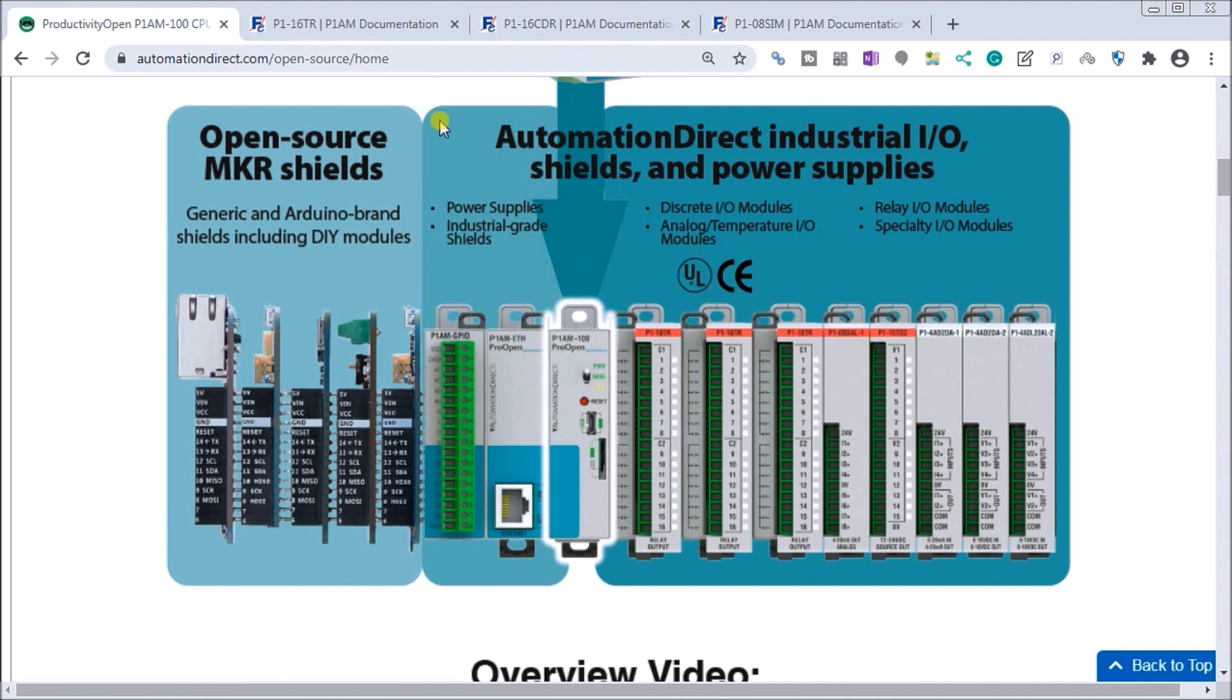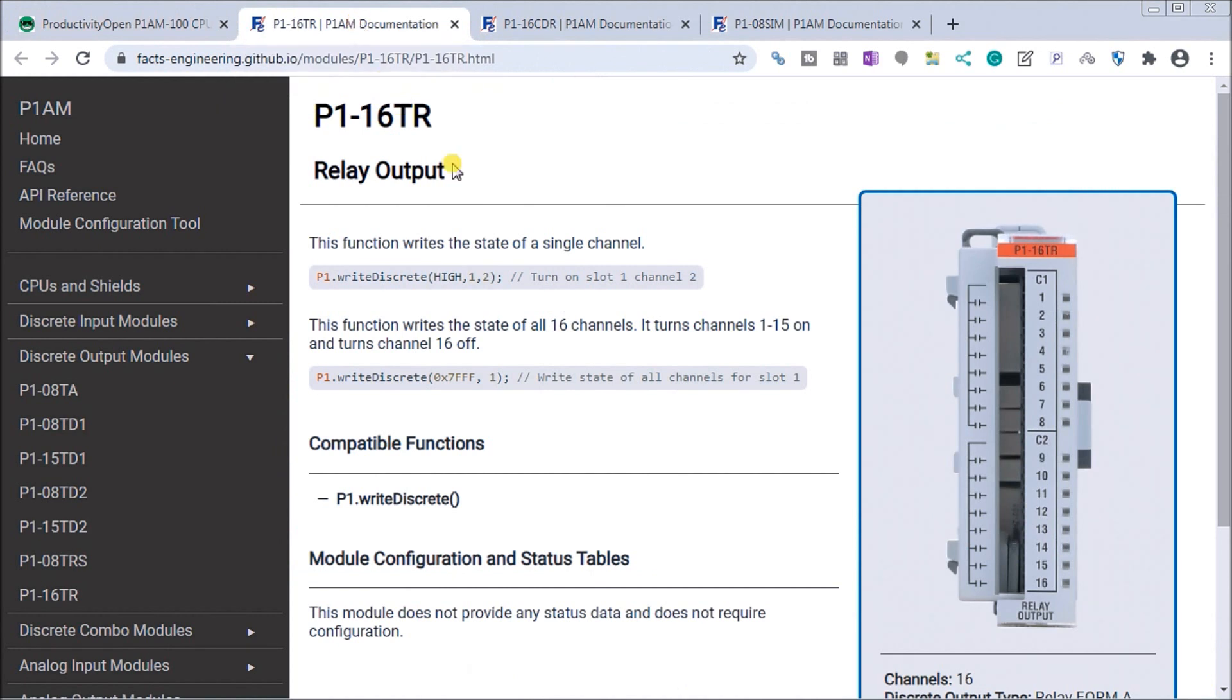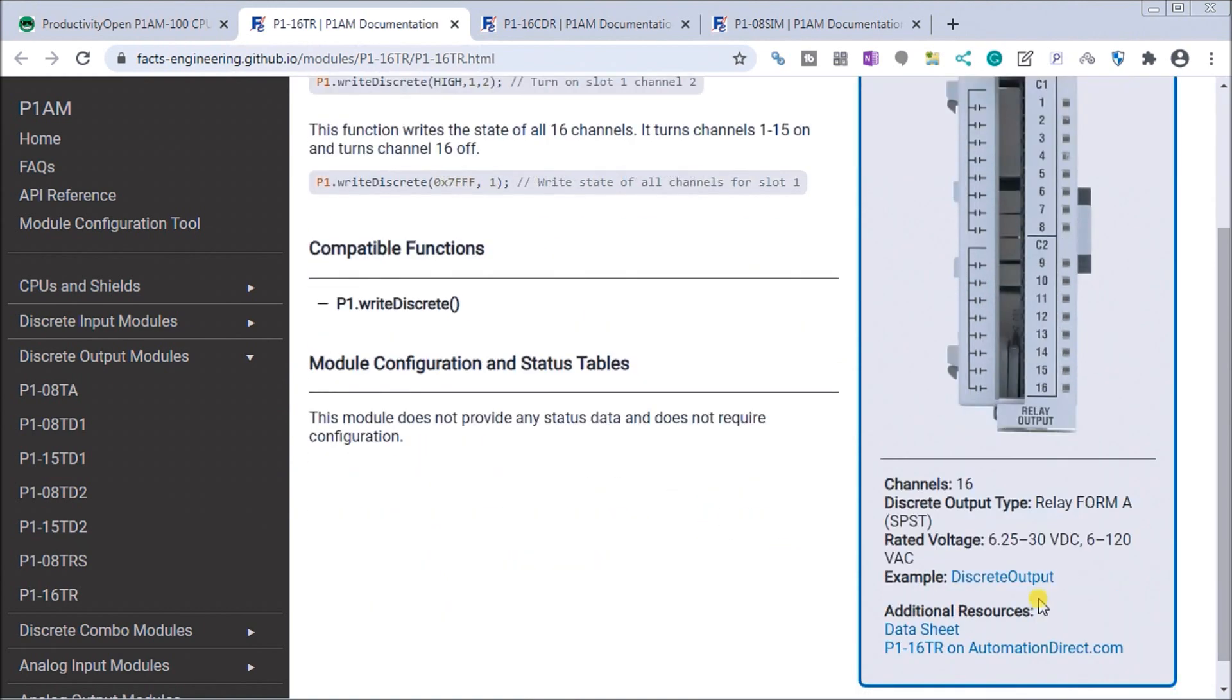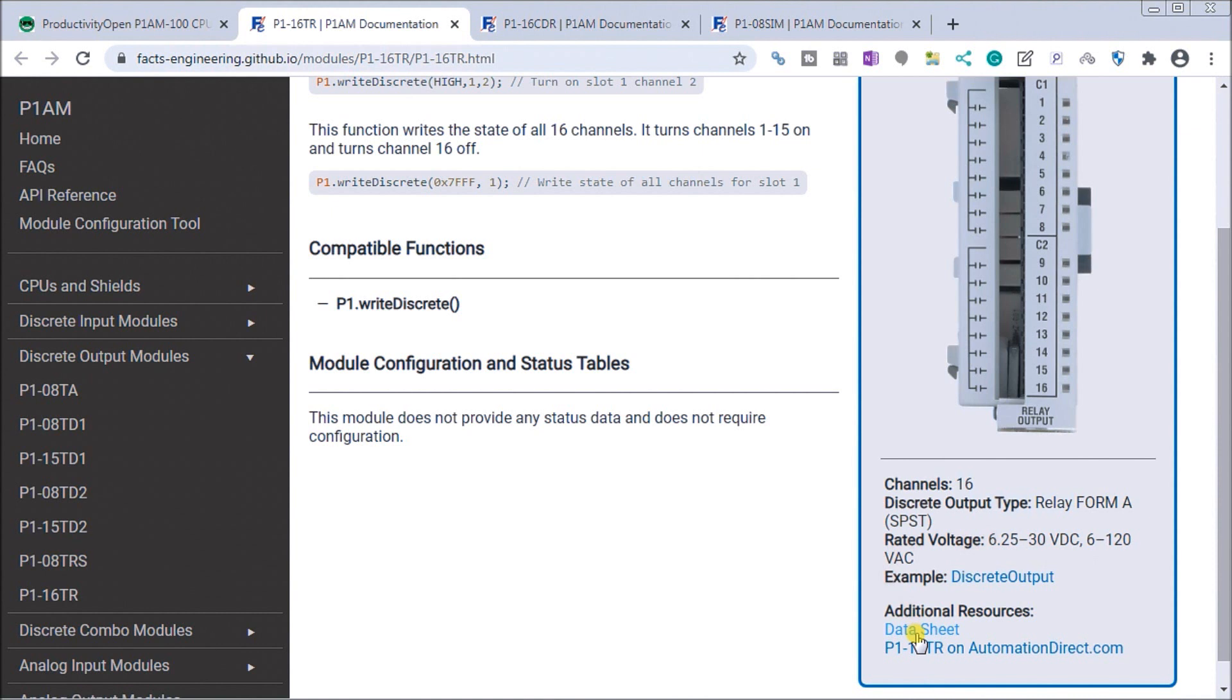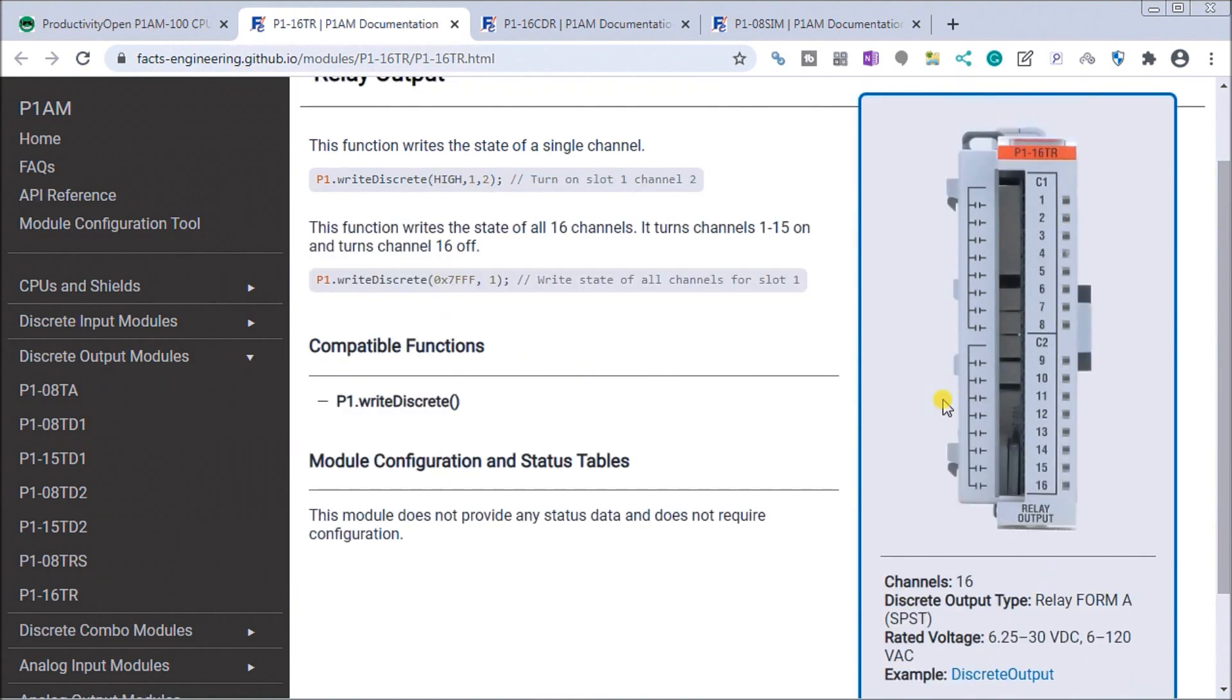The modules we're going to add is the P1-16TR which is the relay output. We have 16 relay outputs with rated voltages of 6.25 to 30 volt DC, 6 to 120 volt AC that we can control. We have two commons for this unit and it's a single pole, single throw, each contact of that relay.